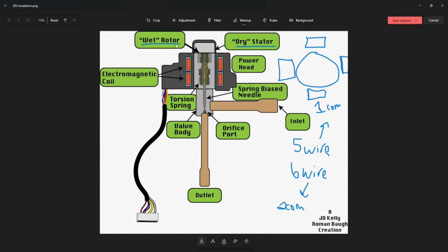You have a stator and a rotor. The rotor does the spinning. The stator is the piece that stays in place that the rotor is actually moved by. So the stator is what has the magnetic charges in it, the magnetic coils. The rotor is what actually spins the needle down into the valve. So when you get a call to either open or close the needle of an EEV, you get positive and negative charges around the poles.